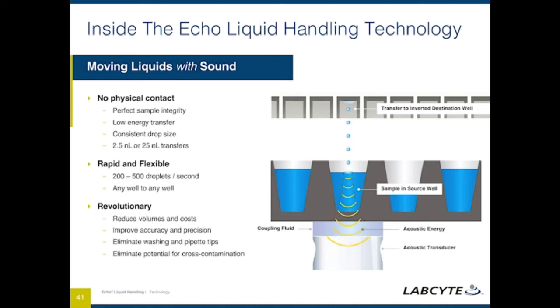For volumes that are greater than either the 2.5 or the 25 nanoliter, we're essentially just ejecting multiple droplets in succession. And those droplets can be ejected into either a dry well or a well that already contains some fluid in it. That ejection process is extremely rapid, so we can eject those droplets at rates anywhere between 200 to 500 droplets per second. We can also position that acoustic transducer under any of the wells of the source plate and position any destination well above the transducer. And so that enables us to do any well to any well transfer.